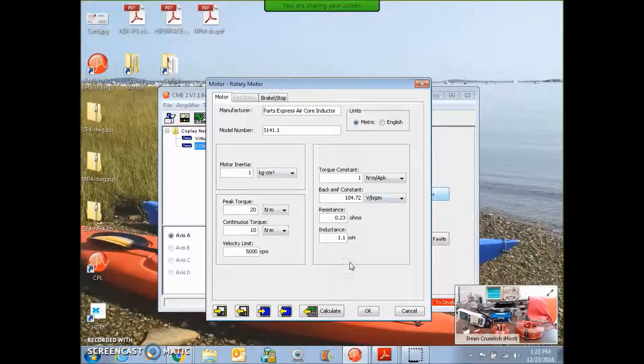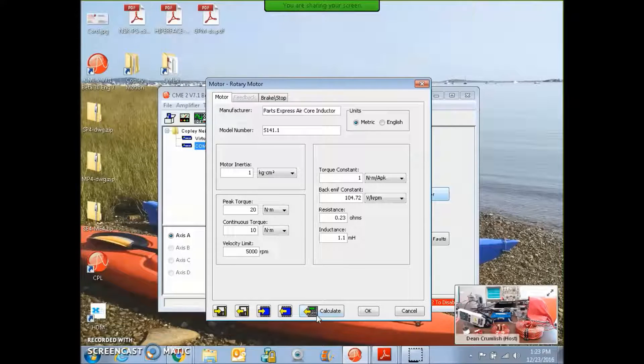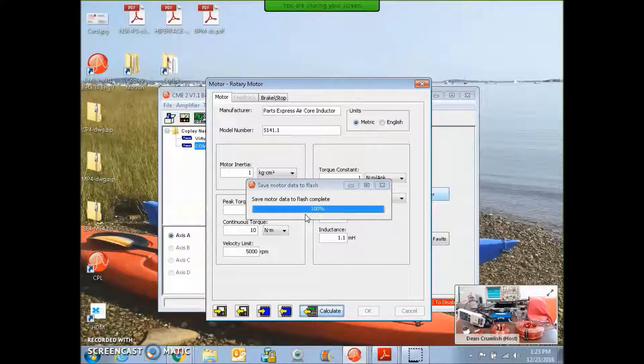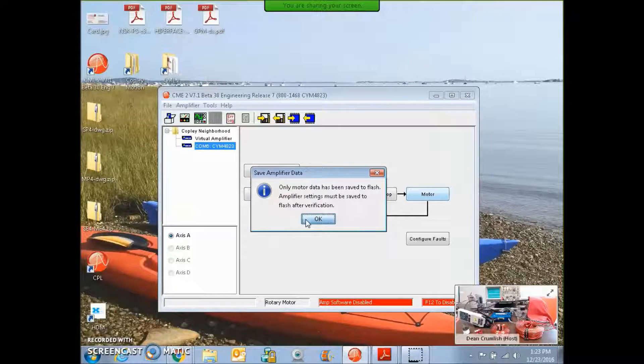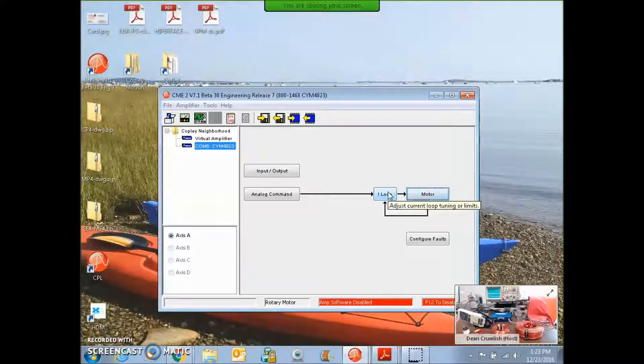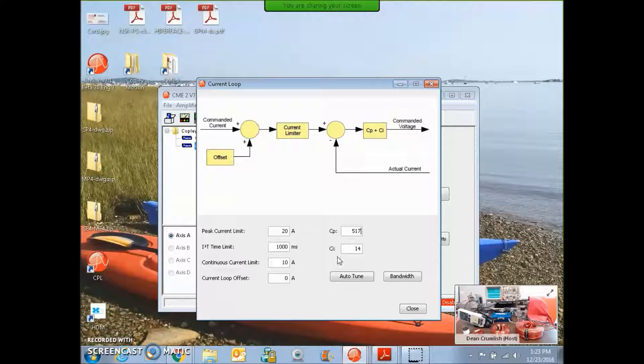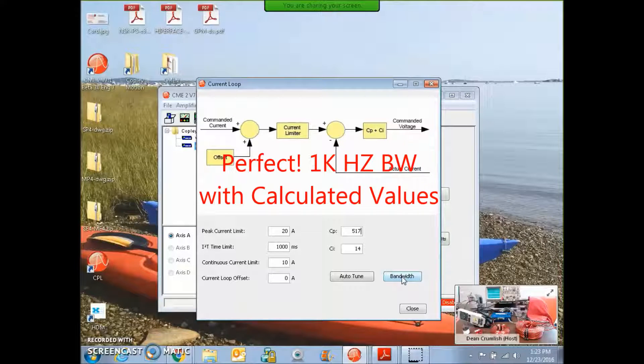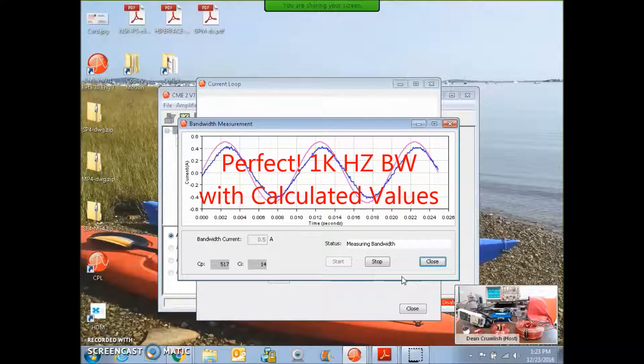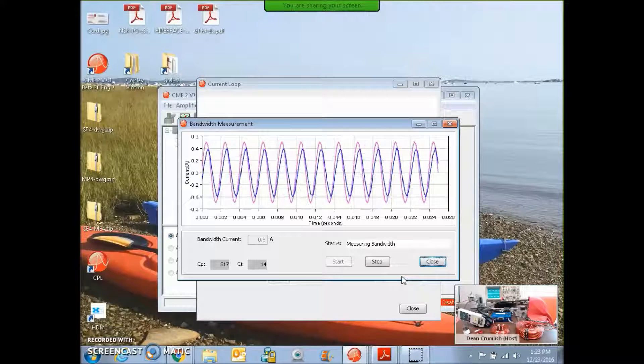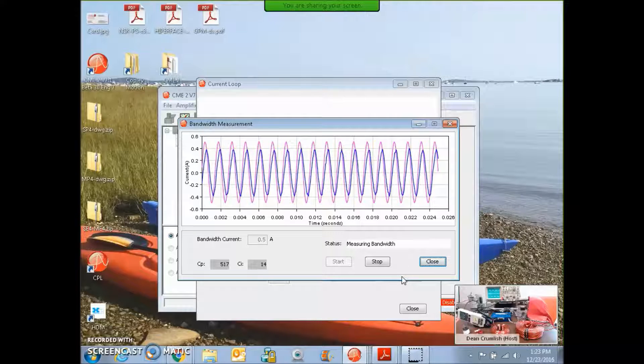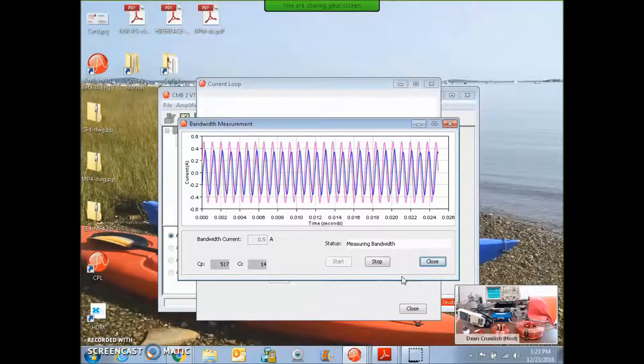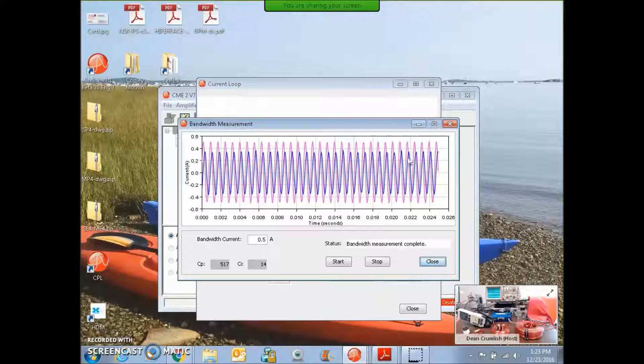I put that in and I hit calculate to get the initial calculated tuning values for the current loop based on the motors inductance and somewhat the resistance. We get some current loop values that are calculated and these will typically give us a kilohertz of current loop bandwidth based on good data. We can run the bandwidth test to check that out. Sometimes it's plus or minus a little bit, but it looks like we got about that.